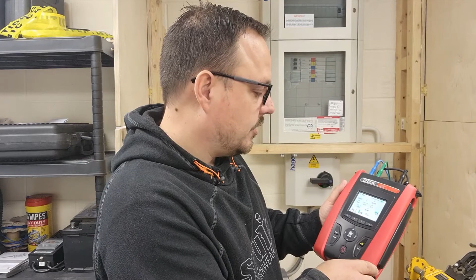So it's measuring 242 volts, 5 amps, 50 hertz near enough, and we've got 1.2 kilowatts on there, 1.2 kVA, and a power factor of 0.99. We'll just pop that back down, and that's because in the corner there I've got a heater plugged in. There's nothing else on this circuit at all at the moment, just the heater in the corner.